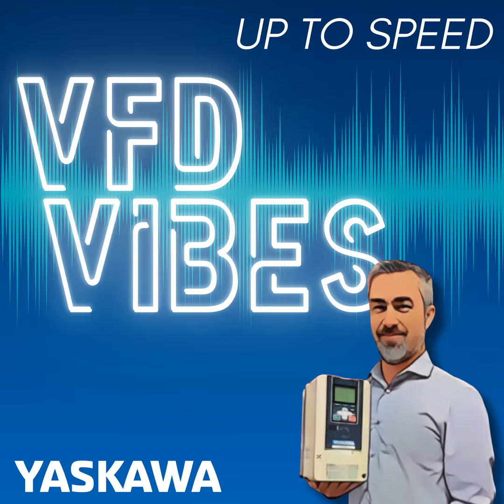Very good point. Yep. When you're going through this startup, a seasoned drive pro like yourself can probably fly through parameters and do a lot of setup off the top of your head, but are there any tools in the drive that help somebody get it programmed properly right out of the gate? Sure. Yeah. Probably the most, or one of the most important aspects of a startup would be to auto-tune the motor. And what do we mean by that? What you can do is have the drive do this procedure, and there's two different types of auto-tuning.